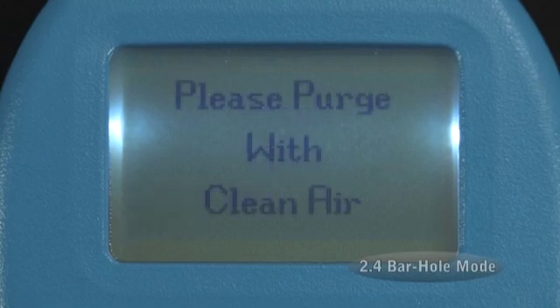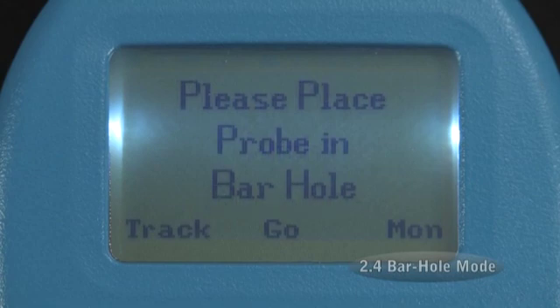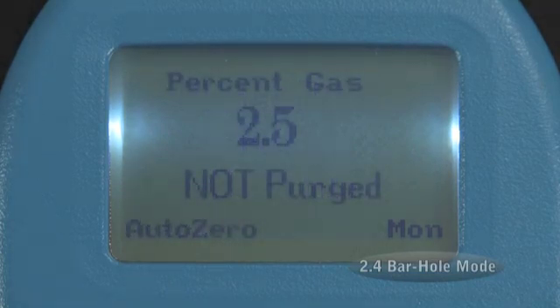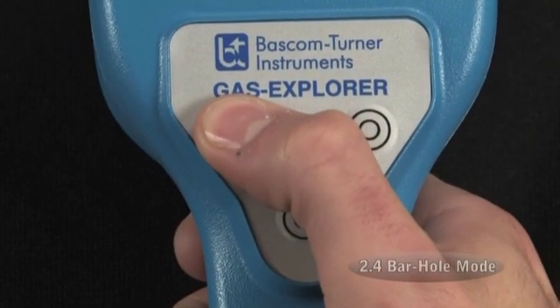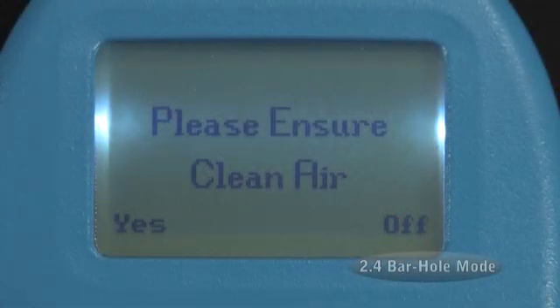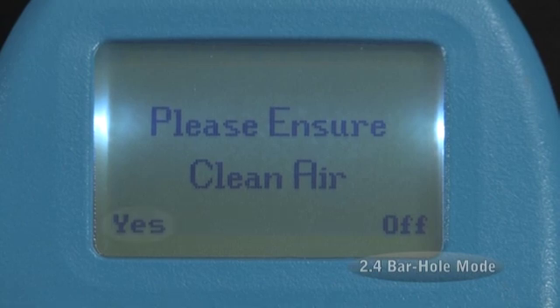In either case, you will be asked to please purge with clean air. If no gas is found, the pump will stop running and you will see a display telling you to place the probe in the bar hole. If gas is found, the display will show its concentration in percent gas and will display Not Purged. The left button on the display will now be marked Auto Zero. When this is pressed, the display will show Please ensure clean air. To run the Auto Zero, press the left button marked Yes.